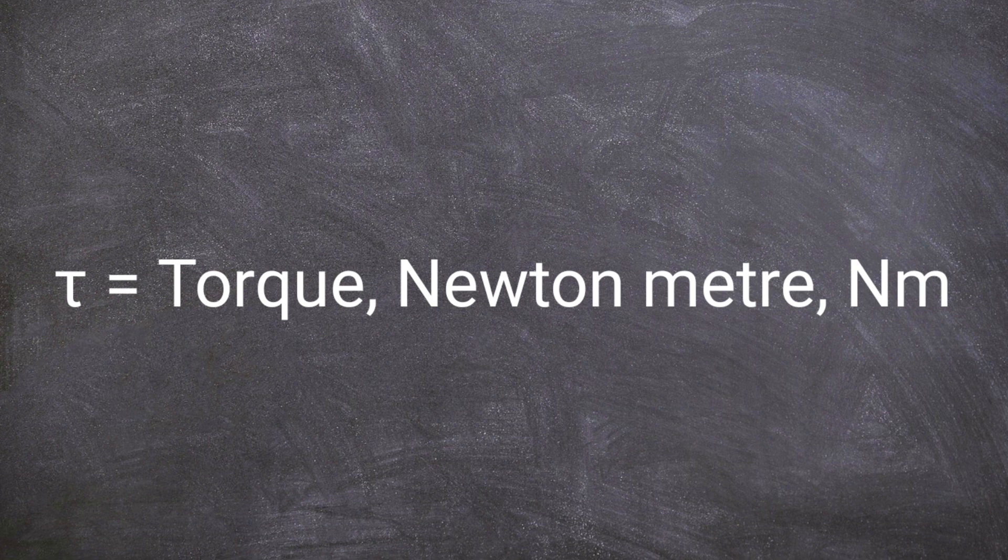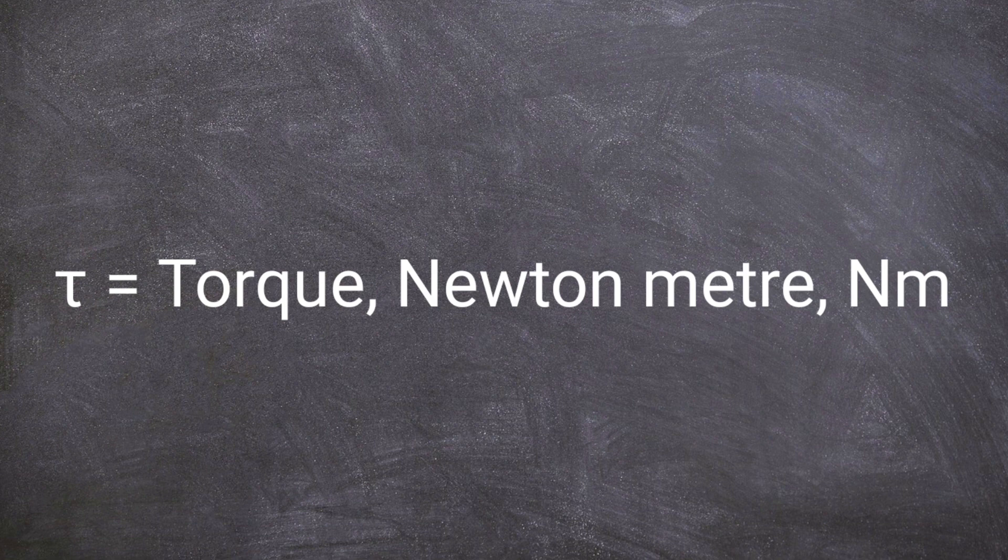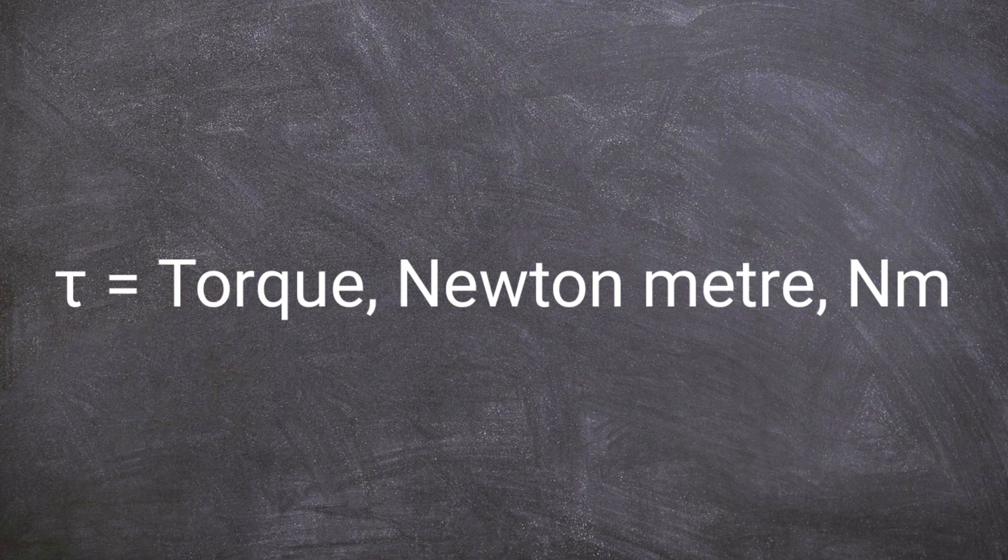Now, my apologies if you're watching this in the United States of America, as I believe the unit that you use to measure torque there is the foot pound. But obviously, under the SI system, we use the Newton meter. And of course, the other area where we might come across this concept of torque is when we're connecting up consumer units or distribution boards, because we know that the circuit breaker screws and the screws in the neutral and earth bars have to be set to certain torque values. So we get the idea that once we reach a certain value of Newton meters with our torque screwdriver, that is tight enough. In effect, we've applied enough turning force to that screw to get it to the right setting.